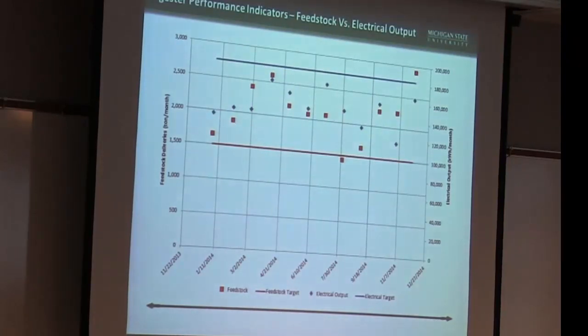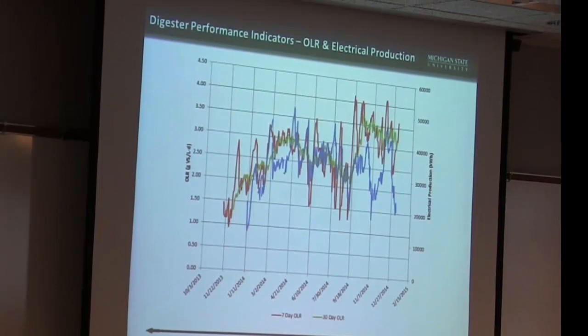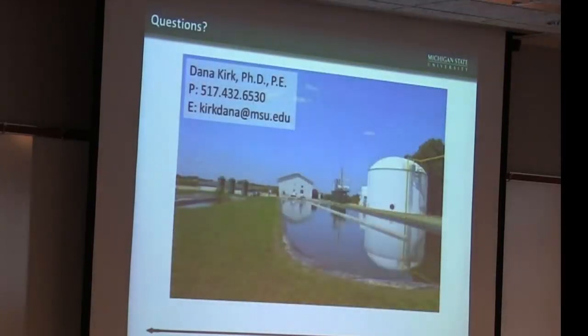The system is working well. The digester itself is performing extremely well — our methane concentration is always 63–65%, which is very high compared to a typical dairy digester running at 52–55%. We're getting the mechanical issues resolved and working out feedstock deliveries and energy densities. Another chart shows organic loading rate and electrical production — we do see a lot of variability, with a relatively smooth range through the summer months and then mechanical issues with the combined heat and power unit causing downtime, especially in November.